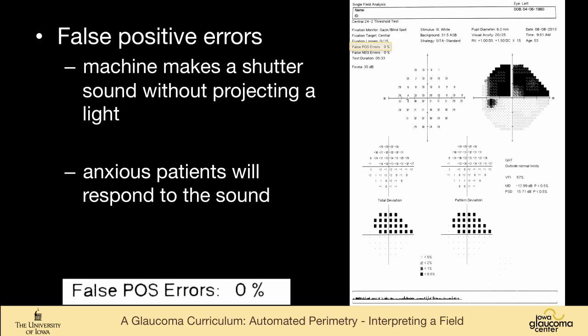So in a false positive, the test for false positivity, the machine makes a sound like a shutter sound without projecting a light. And patients who are anxious, people always think that they're going blind, and so they might be very trigger happy. If they push too often, then those are called false positive errors.